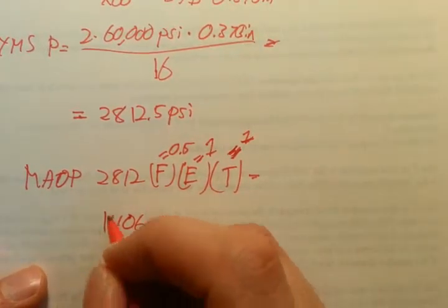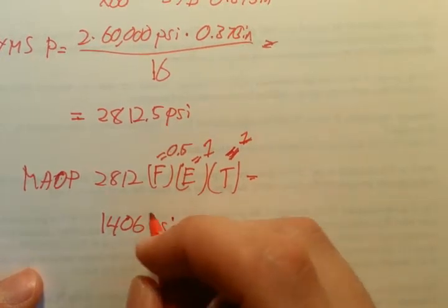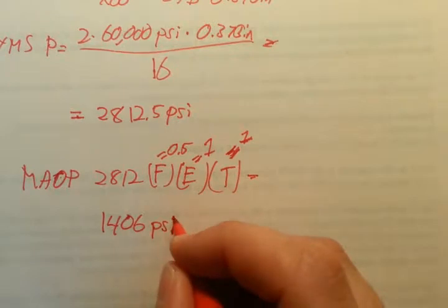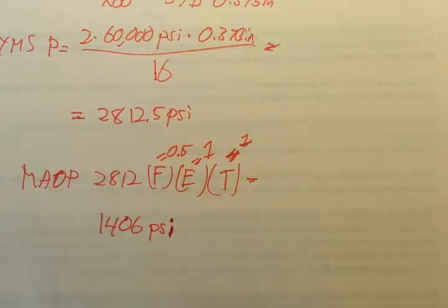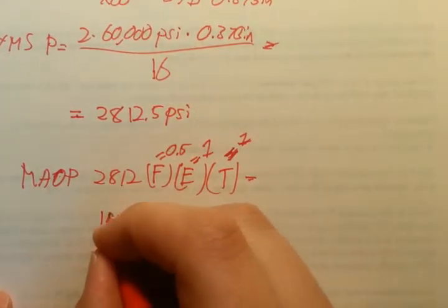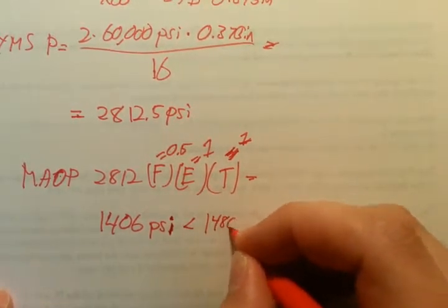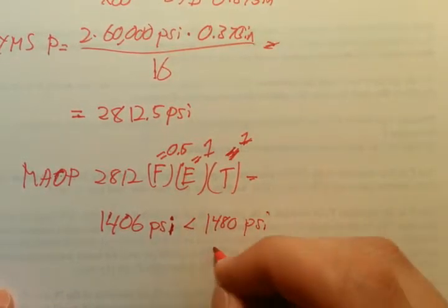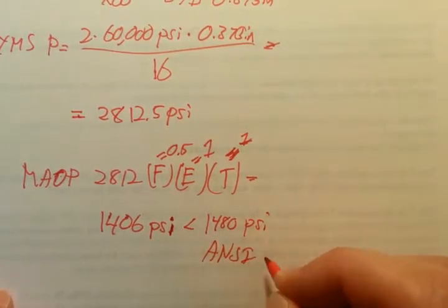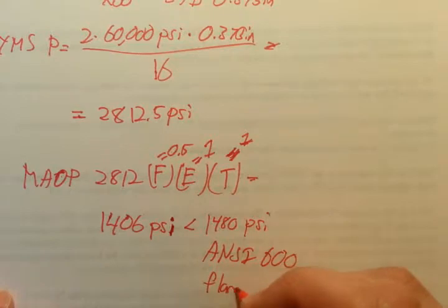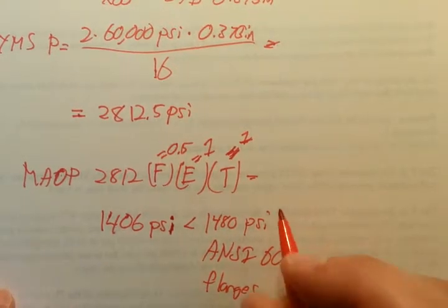So that is for this 16 inch pipeline, that is the maximum allowable operating pressure that DOT wants you to operate at. And that makes sense because that's just below 1480 PSI, which is ANSI 600 maximum rating for flanges and components and valves.